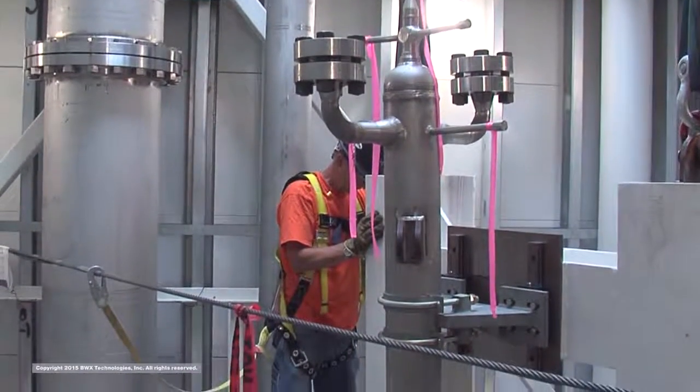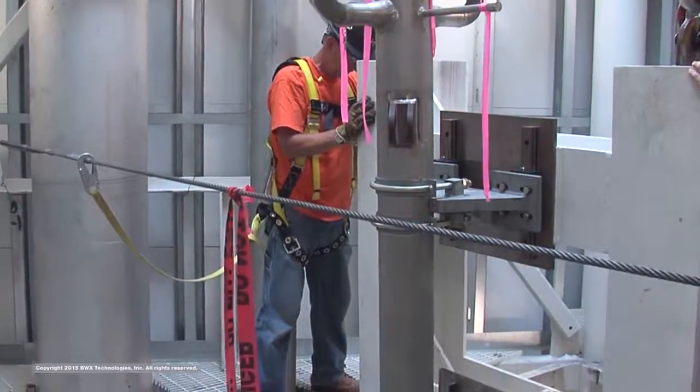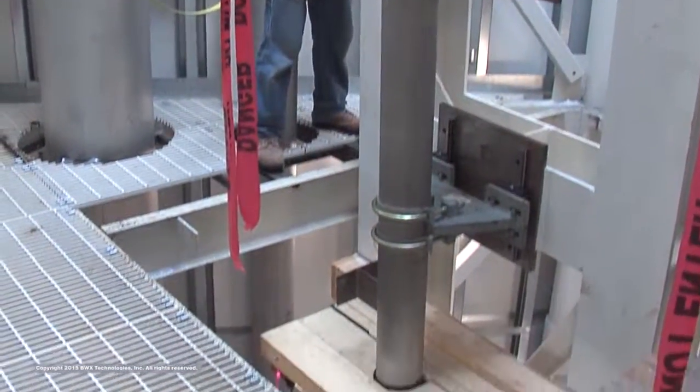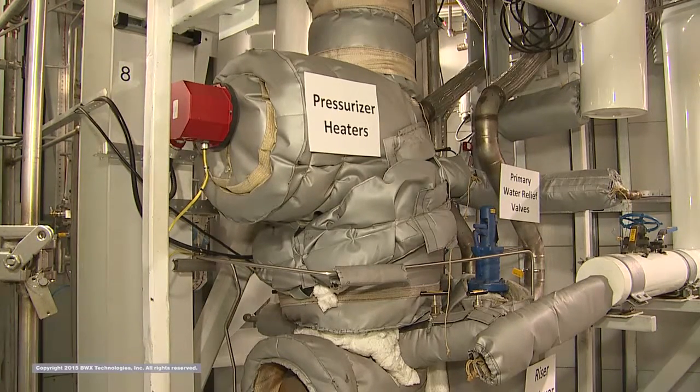The pressurizer measures 9 feet 5 inches in height and communicates with the primary loop. It includes a 6-kilowatt heater and spray nozzle to maintain pressure in the loop. The top of the pressurizer has connections for depressurization simulating passive emergency core cooling and a connection for simulating a spectrum of loss of coolant accident break sizes.